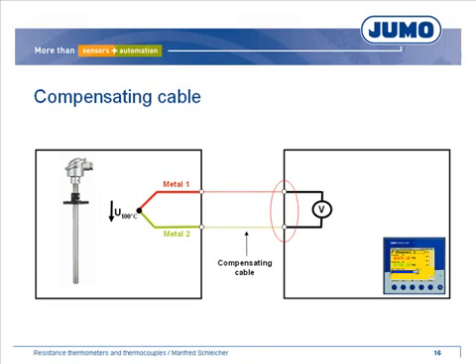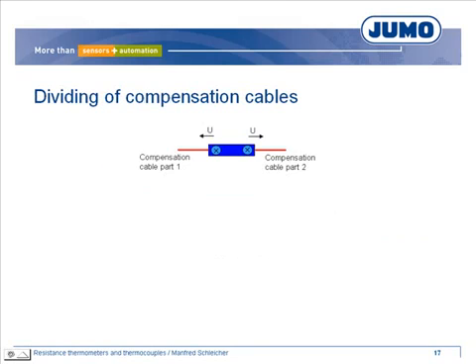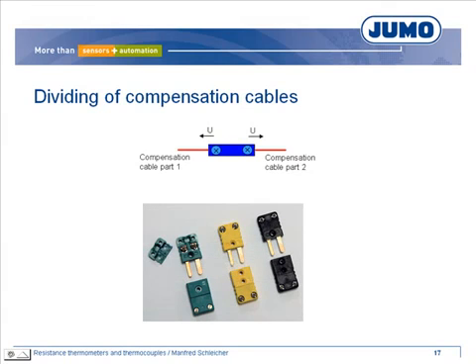You must use the corresponding compensation cables and consider the polarity. By using several sections of compensation cables connected with, for example, luster terminals, new thermocouples arise due to the different materials. The voltages are compensated when the different sections have the same temperature. When the temperature can differ, you must use connectors free of thermoelectric voltage, made of materials with the same thermoelectric characteristics as the thermocouple, and select the correct connector considering polarity.